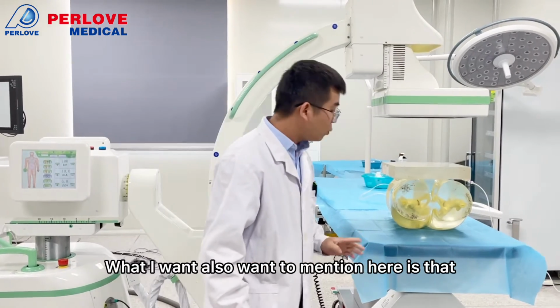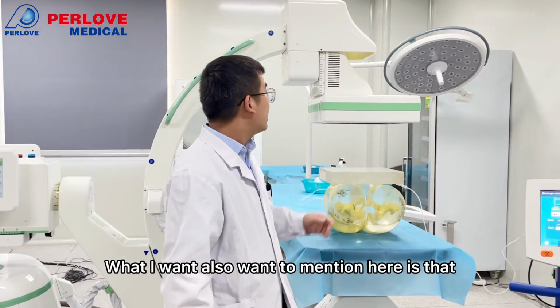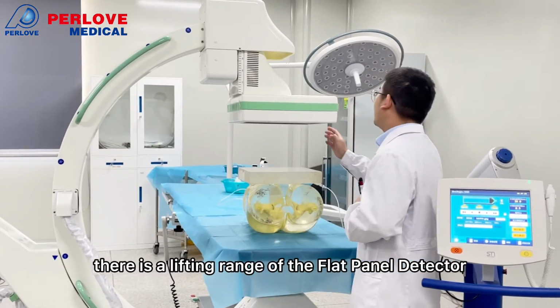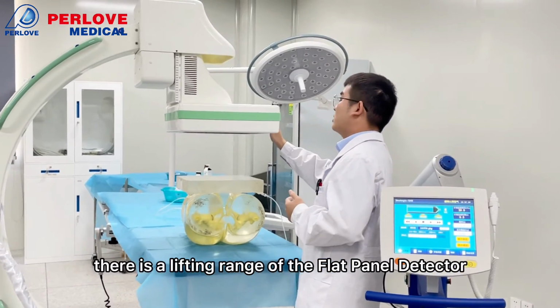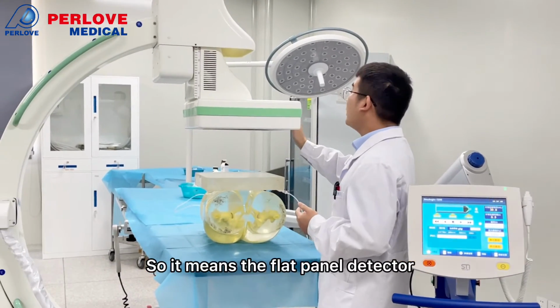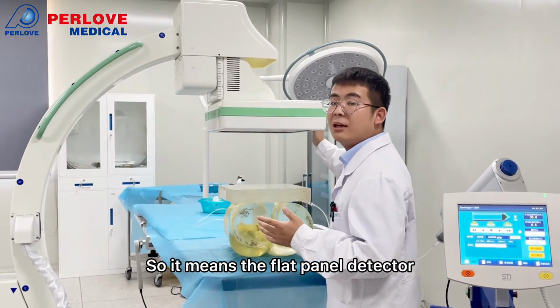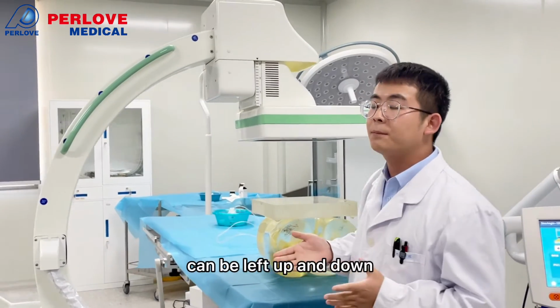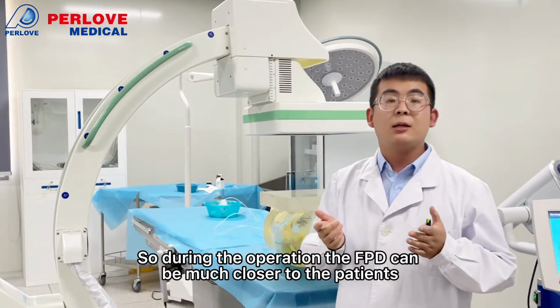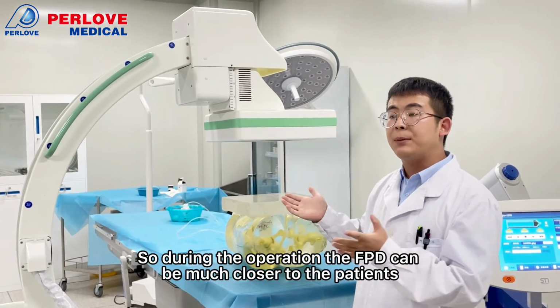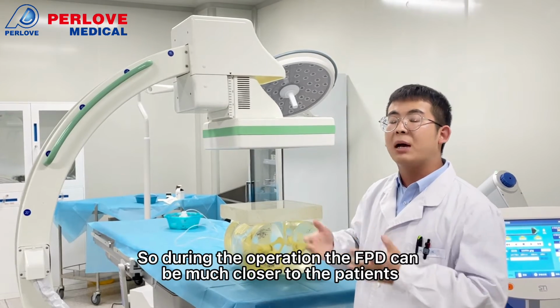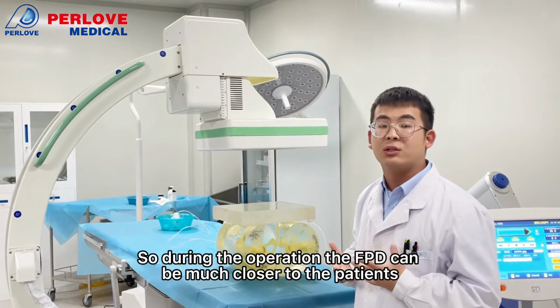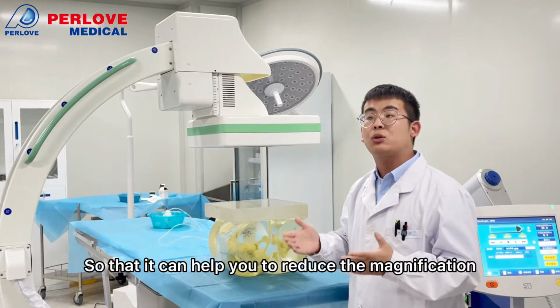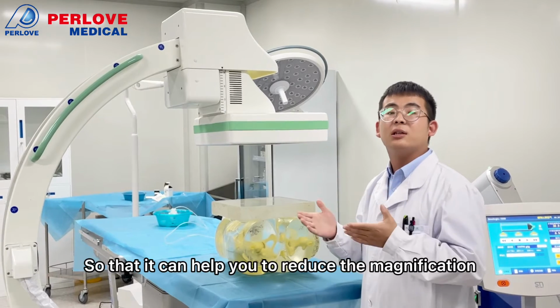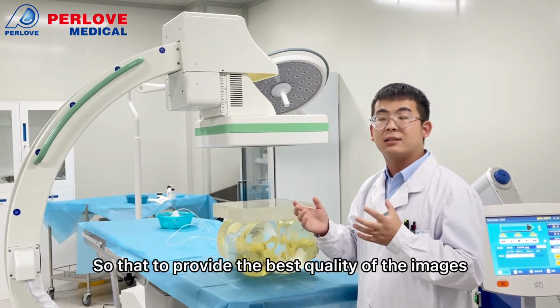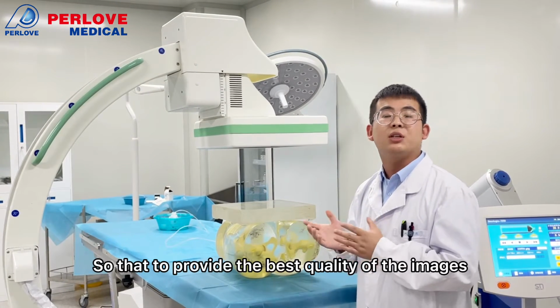What I also want to mention here is that there is a lifting range of the flat panel detector. It means the flat panel detector can be lifted up and down. So during the operation, the FPD can be much closer to the patient, which helps you reduce the magnification and provide the best quality of images.